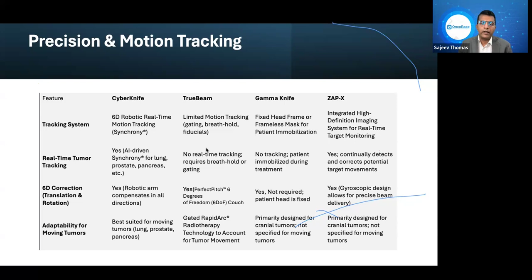So speed and treatment efficiency, if you look at it, we could see the treatment time. CyberKnife is slower, 30 to 90 minutes per session on average. TrueBeam is faster, 5 to 30 minutes per session. Gamma Knife is again long, 30 to 120 minutes per session, depending on the number of isocenters. ZAP-X is moderate. And beam delivery, multiple non-isocentric beams at different angles from the CyberKnife. TrueBeam is VMAT, it is coplanar or non-coplanar arcs. Or the Gamma Knife is multiple cobalt 60 beams. And ZAP-X is gyroscopic.